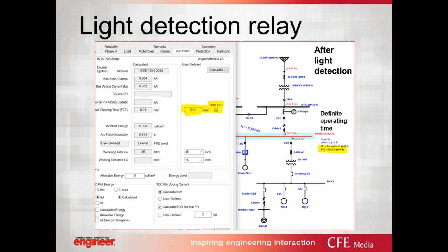0.75. Now, as for how we implement it, realistically at this point I have not seen any software that can do the same thing I showed you with ZSI, implementing it directly. However, we are able to utilize a fixed time for this approach. Let's assume the light detection takes a conservative number like 10 milliseconds. Therefore, on this bus, switchgear A, the fixed FCT is about 0.01 seconds. That's the way we're able to implement this approach for the time being.